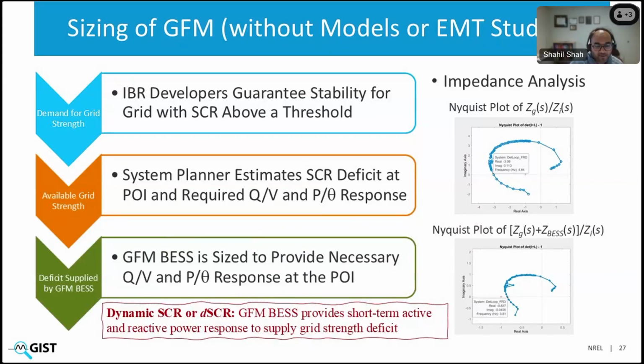So now, how do we use this approach for sizing grid forming resources without models or EMT studies? That is one of the main objectives here. How we can do that is we start with the fact that IBR developers can guarantee stability for a grid with SCR above a particular threshold. Usually, most modern IBRs remain stable when the short circuit ratio, or grid strength, is more than SCR of 3.